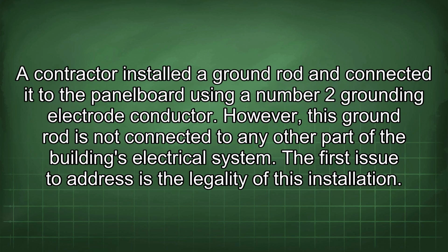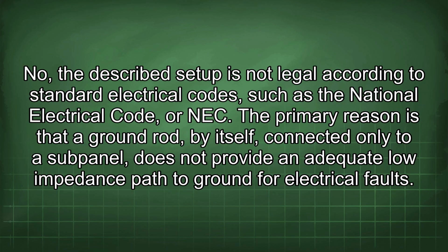A contractor installed a ground rod and connected it to the panel board using a number 2 grounding electrode conductor. However, this ground rod is not connected to any other part of the building's electrical system. The first issue to address is the legality of this installation. No, the described setup is not legal according to standard electrical codes such as the National Electrical Code, or NEC.